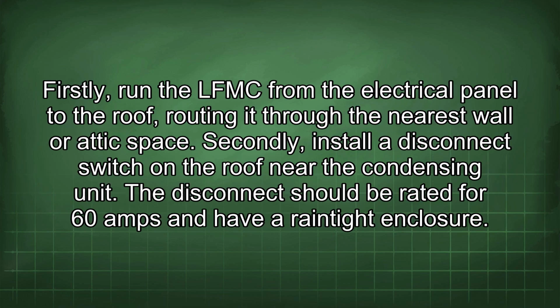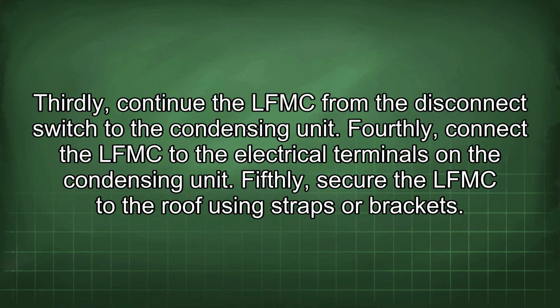Firstly, run the LFMC from the electrical panel to the roof, routing it through the nearest wall or attic space. Secondly, install a disconnect switch on the roof near the condensing unit. The disconnect should be rated for 60 amps and have a rain-tight enclosure. Thirdly, continue the LFMC from the disconnect switch to the condensing unit. Fourthly, connect the LFMC to the electrical terminals on the condensing unit.